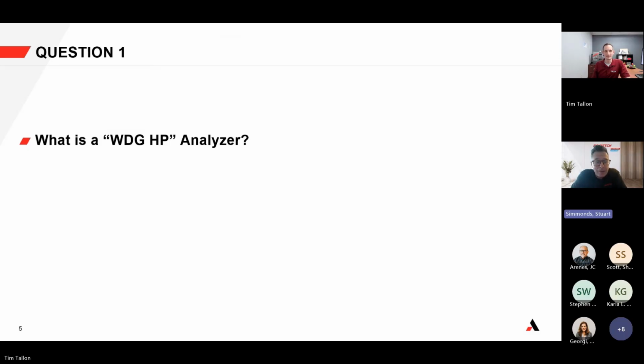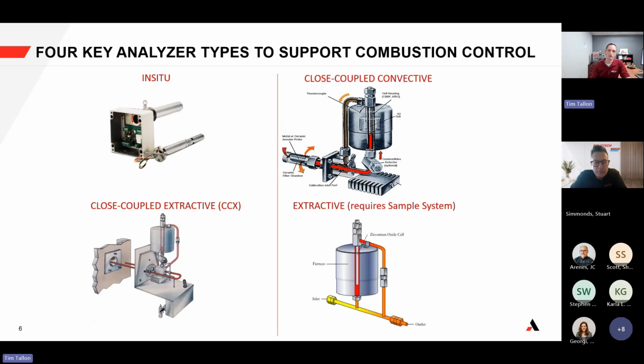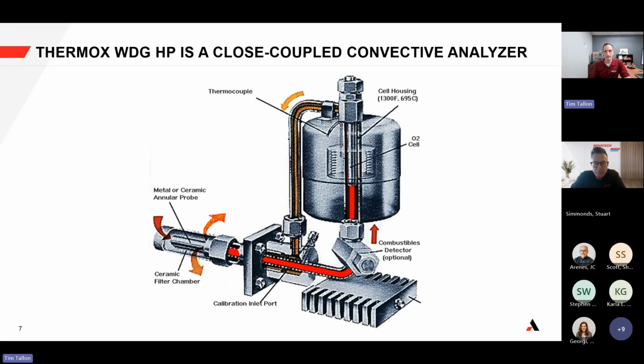Because as I said in the beginning, it is unique to Thermox. Nobody else quite makes an analyzer like this. So why don't we just explain from the beginning, what is the HP analyzer that Thermox have made? Sure, that's a great question, Stuart. And just to put it in perspective, there's 4 key analyzer types for combustion control. There's the in situ type, the close-coupled extractive type, the extractive type, and then the close-coupled convective type. And so the HP is a convective type of analyzer, close-coupled on the process flange, designed to support high particulate applications. It's a pretty nuanced measurement that doesn't have any aspirator, and that's one way to handle those high particulate applications. So in a nutshell, that's the HP.